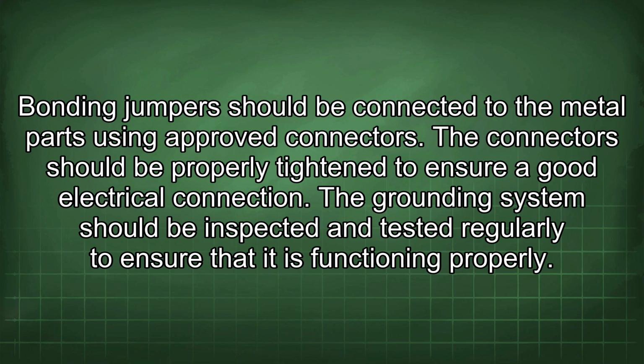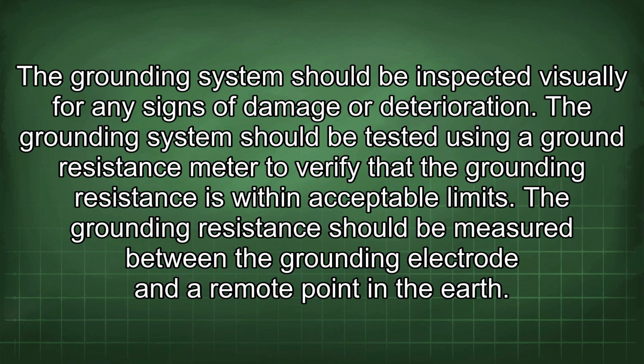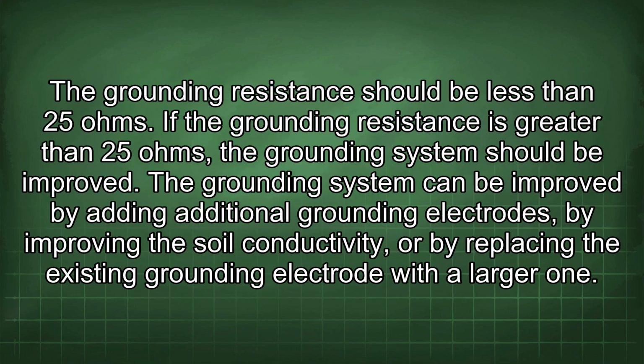The grounding system should be inspected and tested regularly to ensure that it is functioning properly. The grounding system should be inspected visually for any signs of damage or deterioration. The grounding system should be tested using a ground resistance meter to verify that the grounding resistance is within acceptable limits. The grounding resistance should be measured between the grounding electrode and a remote point in the earth. The grounding resistance should be less than 25 ohms. If the grounding resistance is greater than 25 ohms, the grounding system should be improved.